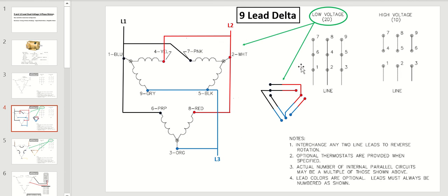For the low voltage connection of the 9-lead delta motor, you see here where it says low voltage 2D. It's actually two separate delta connections, and I'll show you, when you see how this is connected, it's actually parallel coils. It says to power with L1, terminal number 1, number 6, and number 7. And then with L2, we're going to power 2, 4, and 8. And then with L3, we're going to power 3, 5, and 9. So the configuration ends up being 208 to 230 volts across each inductor winding.